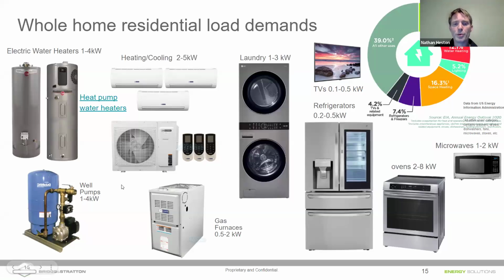Most people don't think about the loads of their gas furnaces, but the blower motors, of course, require certain amounts of power. 200, 300, 400, 500 watts, and 2,000 watts would be fairly large for a blower motor. They're typically smaller than a kilowatt, but that's still a considerable demand. Laundry, when you're either in a heat cycle for water or in a dryer cycle, and the dryer can pull as much as 3 kilowatts.